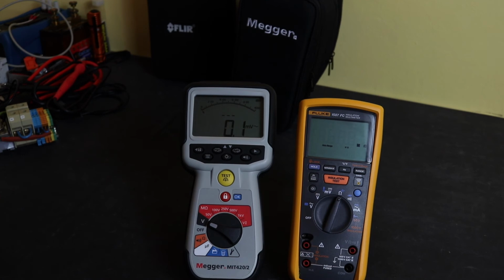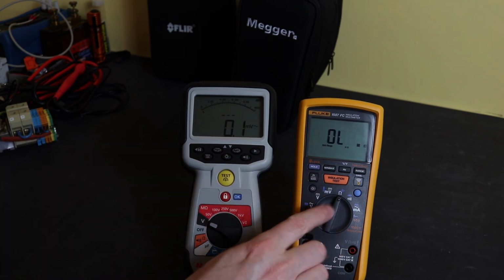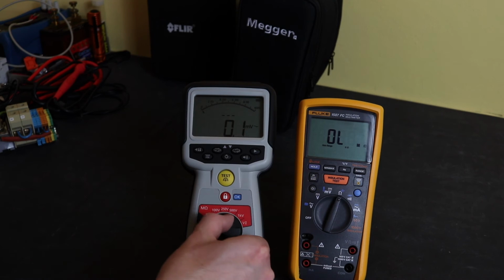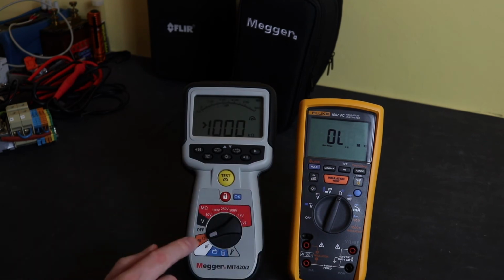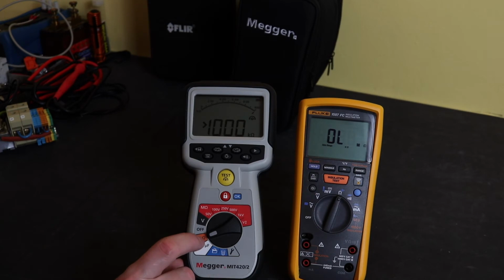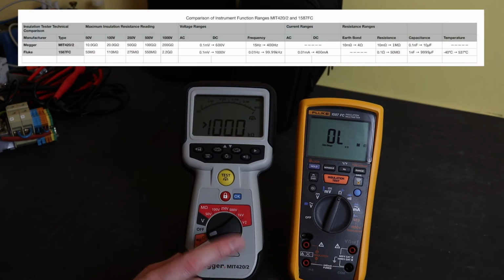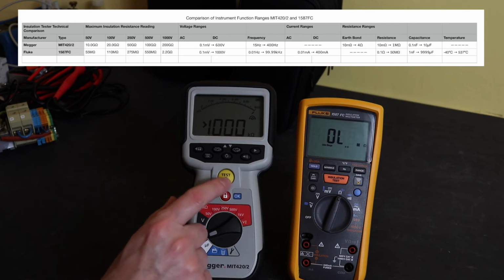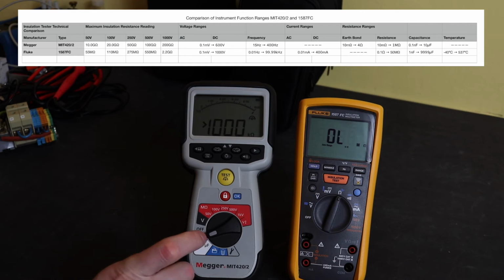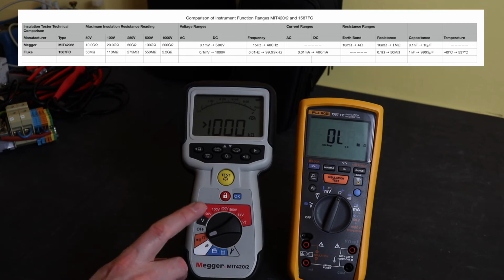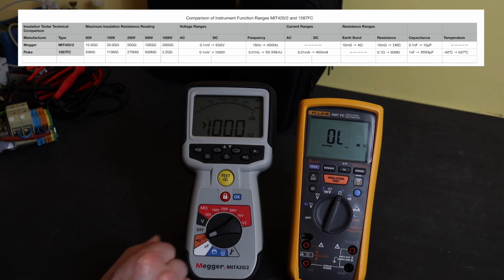Moving further around onto the ohms and capacitance on the Fluke here, you go around. The ohms and capacitance are offered as two separate functions on the Megger instrument. First one is ohms. That's a fully automatic function that measures from 10 milliohms up to 1 megohm. It also has the ability to have a 200 milliamp test current, and you also have a lead zero function as well. The 200 milliamp function will only go up to 4 ohms at 200 milliamps. Beyond that, the current drops down automatically as the resistance increases.